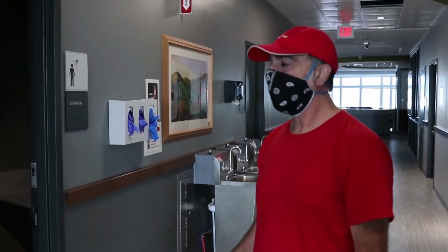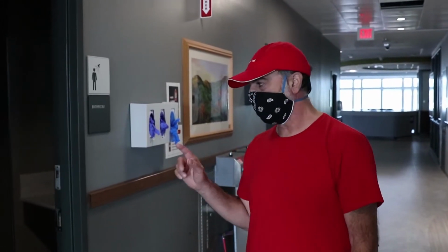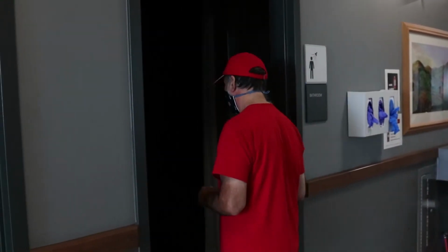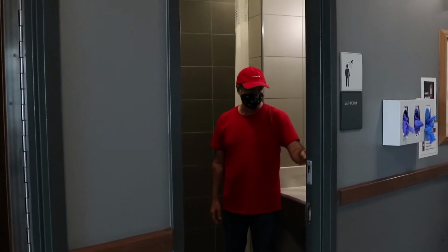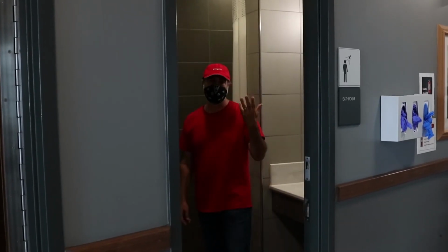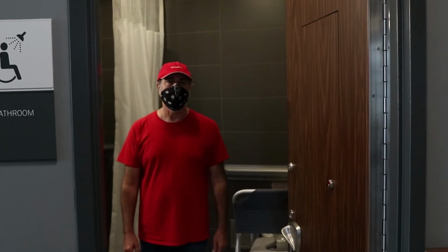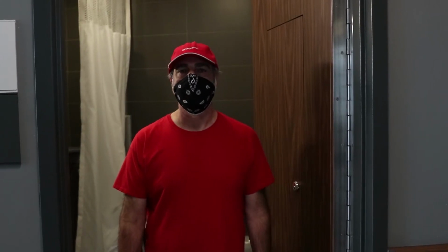Okay, so the bathroom switches, I just want to show you, they're the same switches that I showed you in the bedrooms, except, and I told you you could change the dip switches, but these are set to be automatic. So if I go in the bathroom, it turns the light on automatically. You can, of course, turn it on and off, but as you saw, it turns on automatically. I'll go into the next bathroom just to make sure that works as well. Okay, so that's how the bathrooms work. And that's code for any type of public area, whether it be a public lobby, corridor, or bathroom, that lights need to turn on automatically.